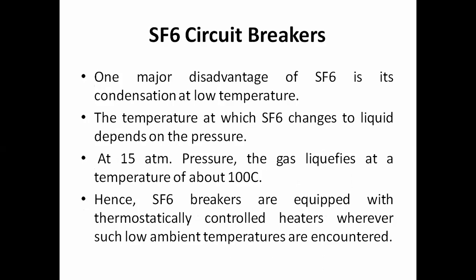One of the most important disadvantages of SF6 gas is its behavior at low temperature, that it can condense at a low temperature. So this is one of the most important disadvantages of the SF6 circuit breaker, because it will condense at low temperature. In order to flow the gas between the moving contact and the fixed contact, if the temperature is very low, then the gas is condensed, and it has to get back into the gaseous form before it can operate in low temperature areas.